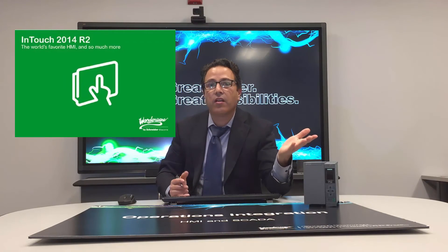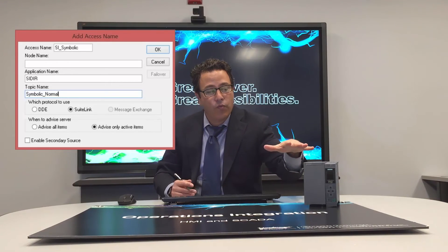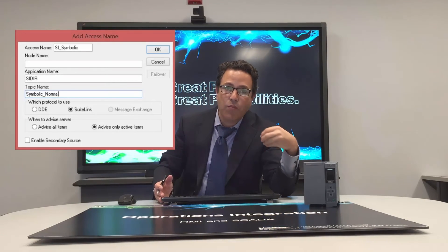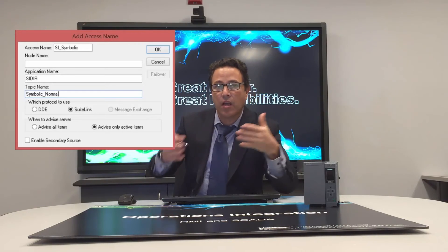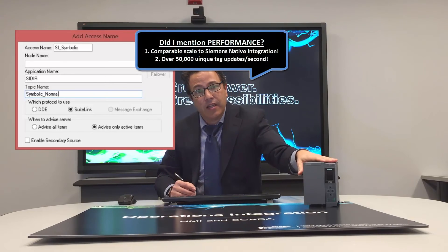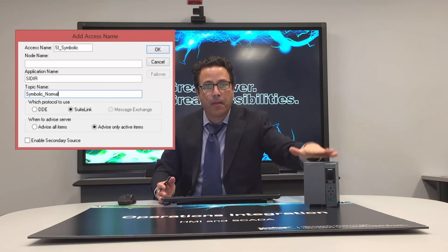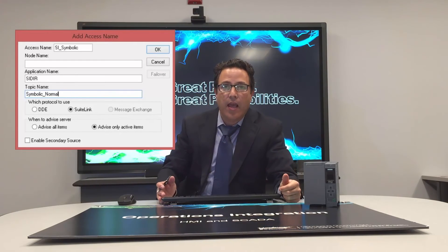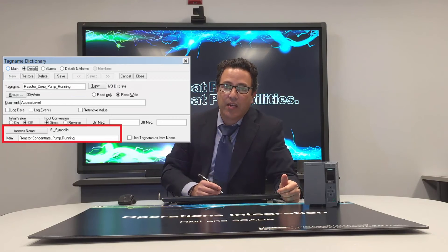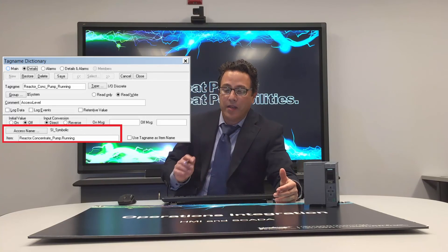Similarly, with InTouch it's just as easy. It leverages the legacy connectivity in InTouch, which is: create your access name connecting to the OIServer. We have kept the same UI experience as the legacy DA servers, and they can coexist with one another. So configure your access name in InTouch — just application name, topic name, and you're good to go. In your InTouch tag names, as usual, you configure your IO item addressing, and it's very simple. No magic there.